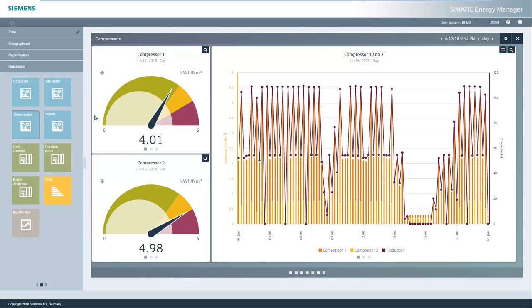In the upper speedometer element, you can see that compressor 1 has a specific energy consumption of 4 kWh per standard cubic meter. This means that compressor 2 is more inefficient than compressor 1.